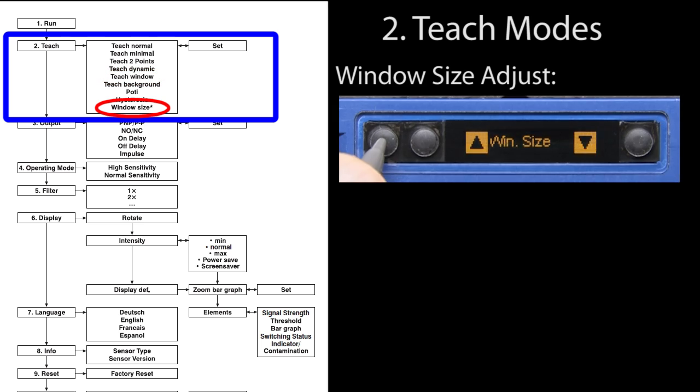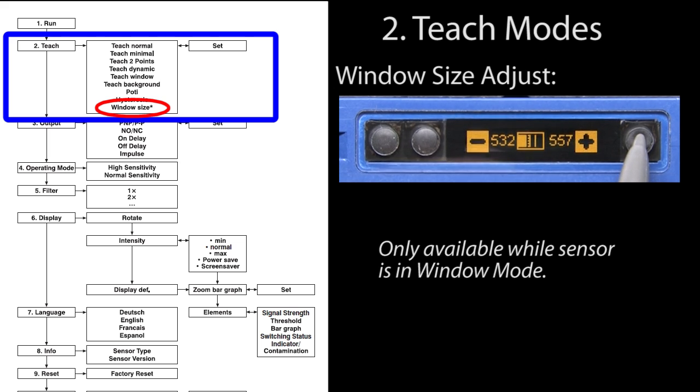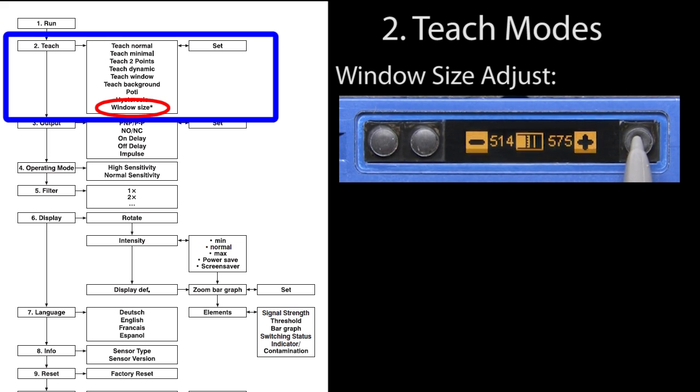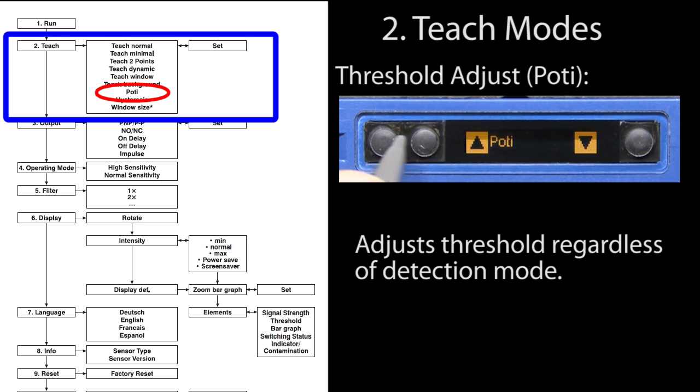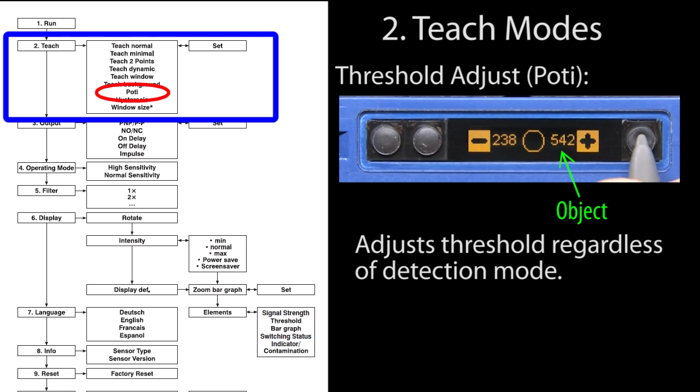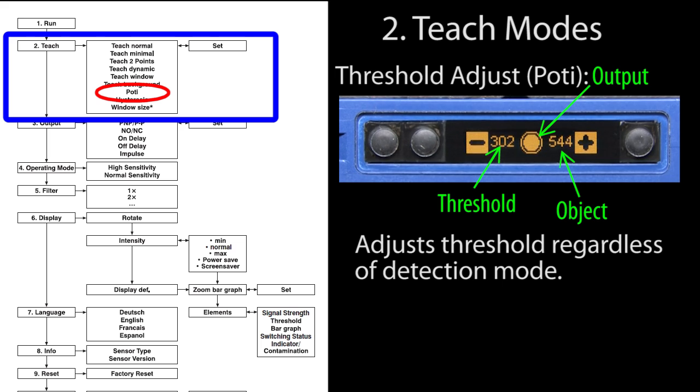You can adjust the size of that window in the window size menu. The window width is currently set to these two values. Just use the plus and minus keys to make it bigger or smaller. You can also move the center of the window or any teach threshold with the potentiometer menu. This number tells you where the current object is. This number is the threshold. Use the plus and minus keys to move that threshold around.